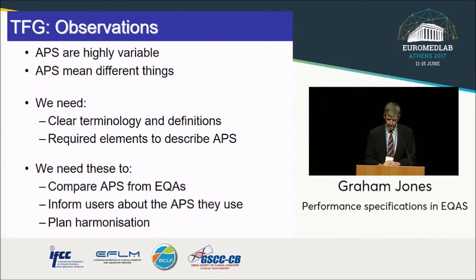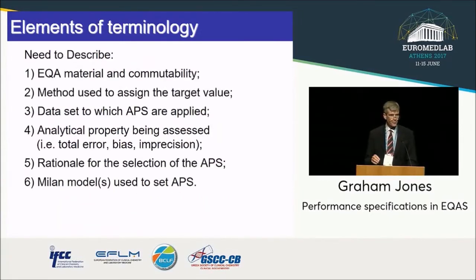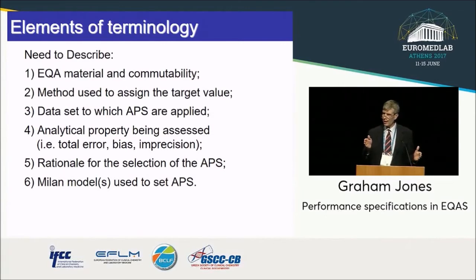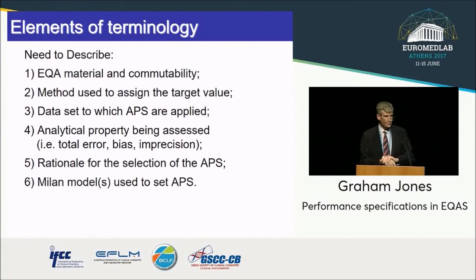We need this terminology and these definitions in order to compare performance specifications from different EQA providers. If you fail in one and pass in another, unless you know why they've been set and have terminology to understand the rationale, you don't know why you've passed or failed. We came up with six elements of terminology to allow a user to truly understand a performance specification: the nature of the material and its commutability, how the target value was assigned, what data it's applied to, what measurement property is being assessed, why it was selected, and which Milan model was used.